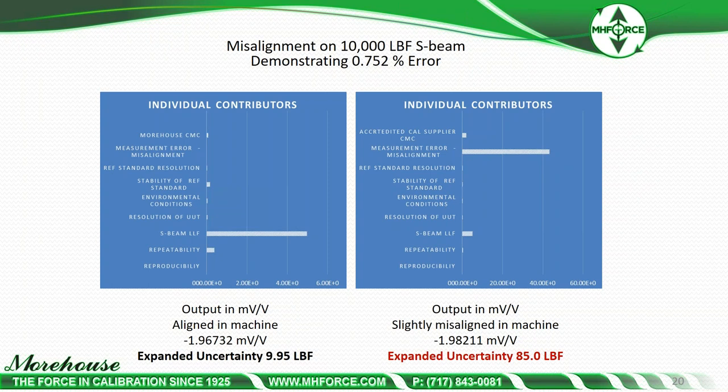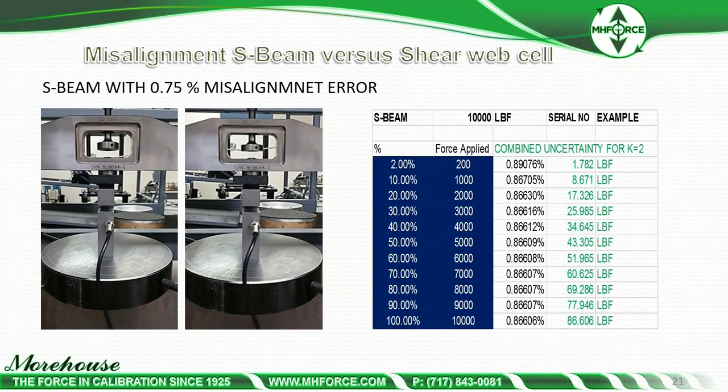From just that eighth-of-an-inch misalignment, if we look at all uncertainty contributors, the expanded uncertainty when aligned and doing an E74 calibration on the left is 9.95 pounds on a 10,000-pound load cell. If we slightly misalign it, our uncertainty jumps from 9.95 to 85 pounds. If we do a combined Welch-Satterthwaite uncertainty analysis, what we think is good to 9.95 pounds becomes 86.606 at the 100% point — and it progressively gets worse.